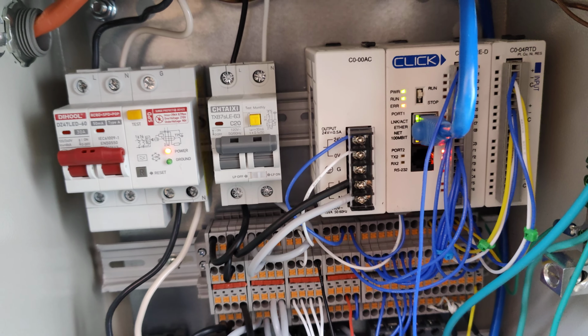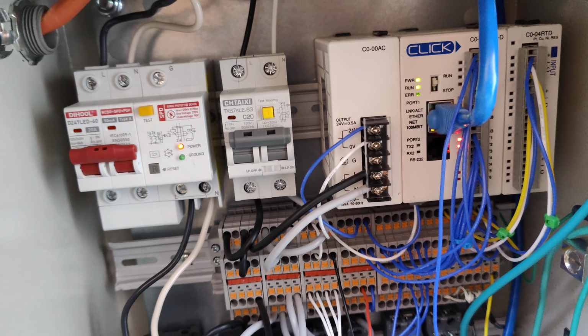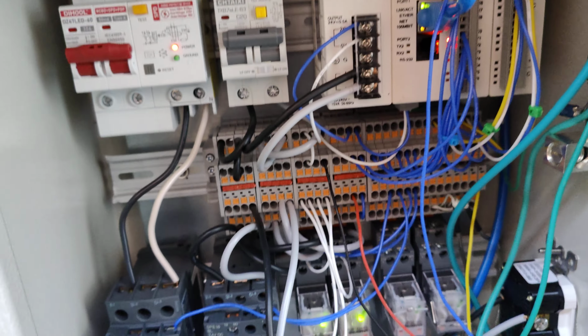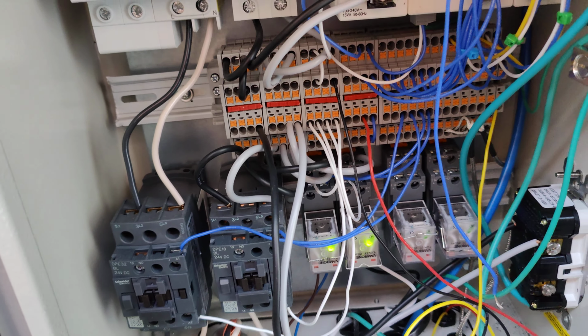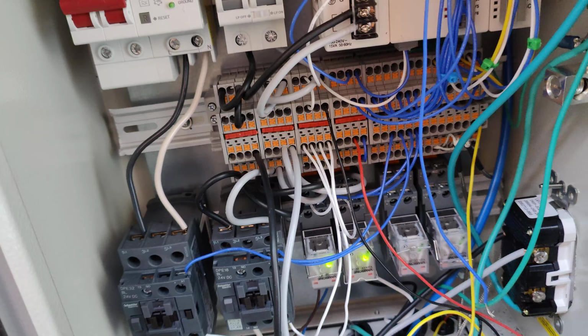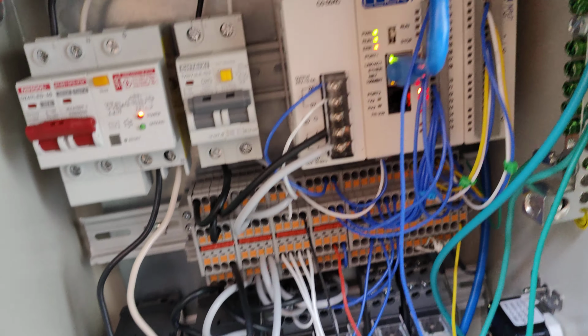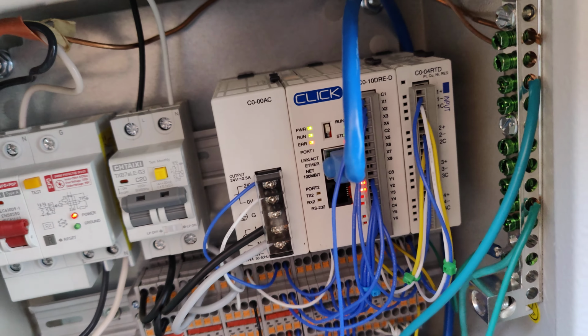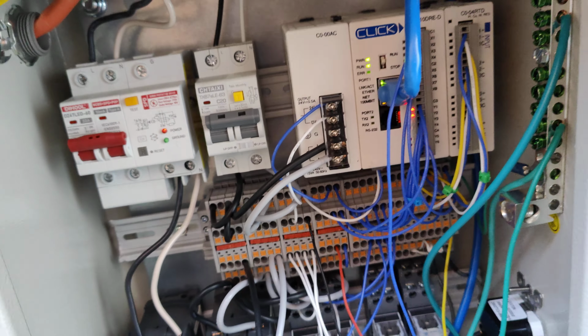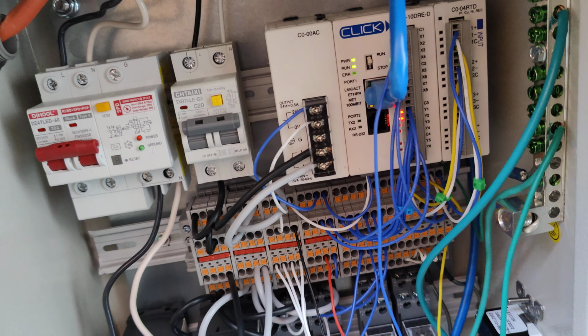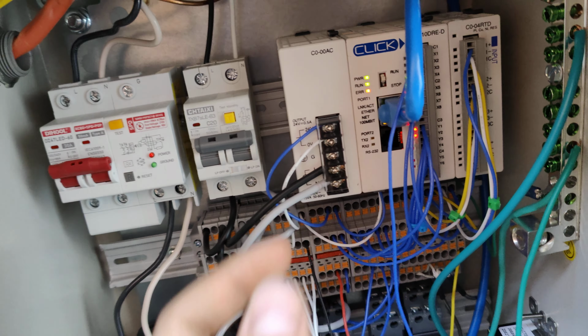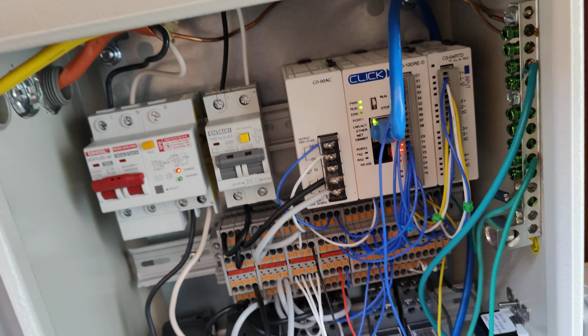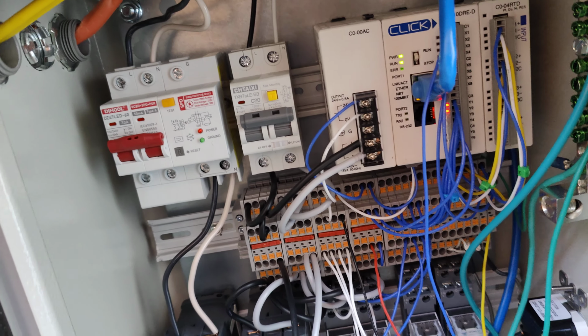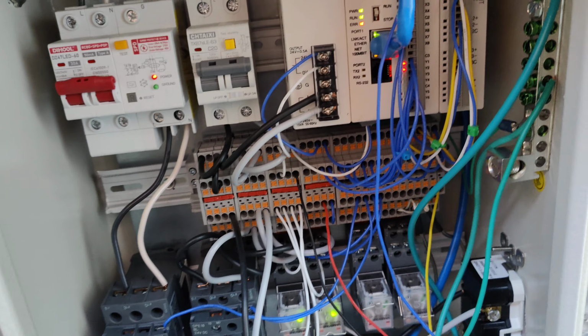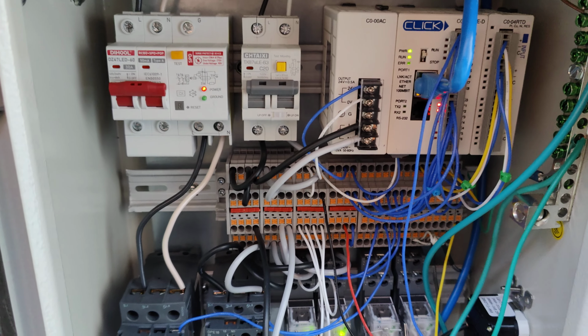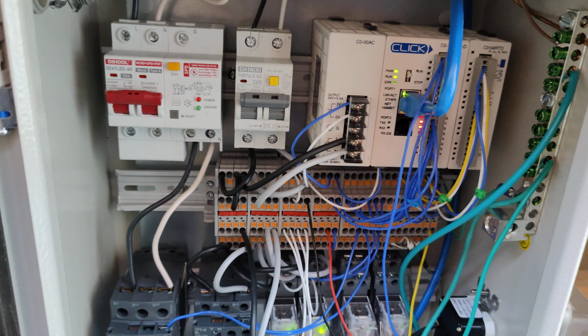Now, I know there's better ways to figure out the polarity and how the internal PLC functions, specifically how your inputs and outputs and what their common wire should be, how it should be wired, but I don't understand it all. So this is a great way to test. Totally safe, I've never burned out an input or an output doing this, and it's low voltage, 24 volts. That's why I love working with PLCs in general, and low voltage, because you can just play around with it and learn everything you possibly can through trial and error. So yeah, that's a good way to test it.